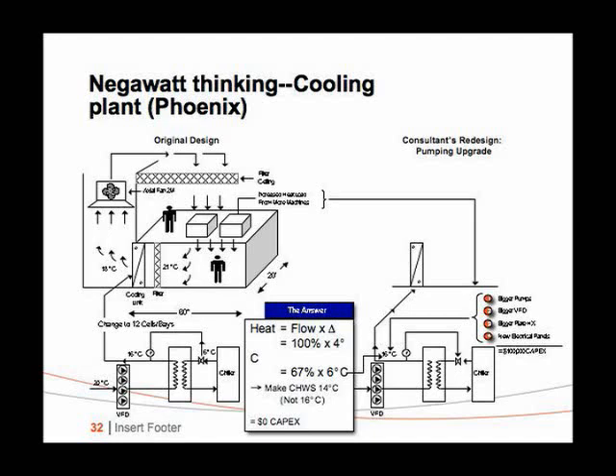Another example of the Negawatt thinking, this time it's from Phoenix, Arizona. So this facilities guy says, Lee, you know, my consultant, which is one of the biggest in the world, has told me that my clean rooms need more cooling water. And the only way to do that is to run new pipes and pumps. And this will take months and, you know, we're going to have to shut down and it's going to cost more than $100,000. So what is the deal?